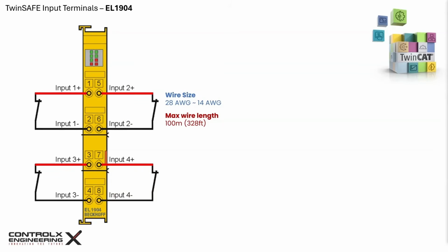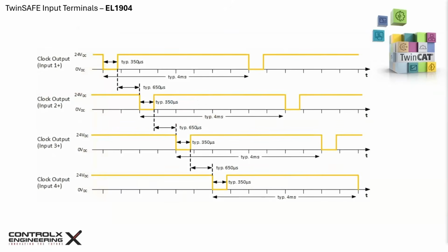Also note that the connection points labeled as input plus and shown here highlighted in red are actually outputs for the test pulses. The connection points labeled as input minus are the actual inputs for those channels. The test pulses are generated separately for each channel in order to be able to detect short circuits between the individual channels of a terminal and also between channels of different terminals. In order to generate test pulses as shown in the diagram, a software setting in TwinSAFE must be set to true for the respective channels. The test cycle for all 4 channels is typically 4 milliseconds. The times between the test pulses of different channels vary, thus allowing better diagnostic detection.